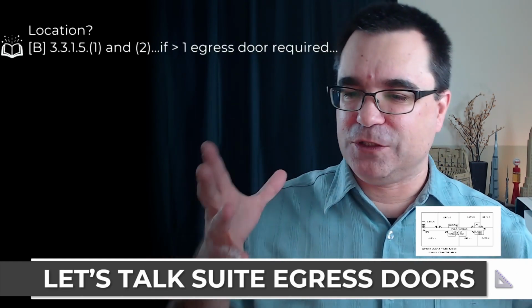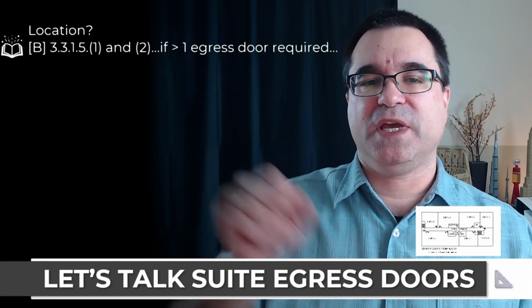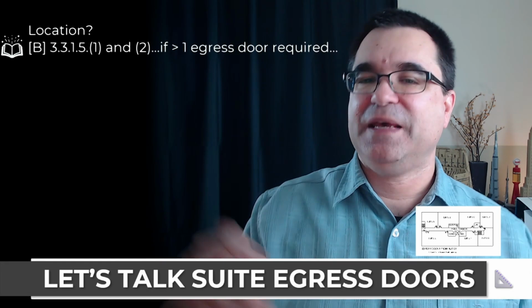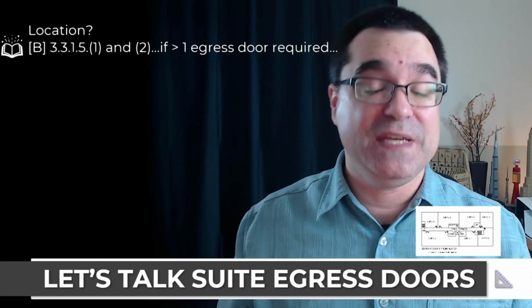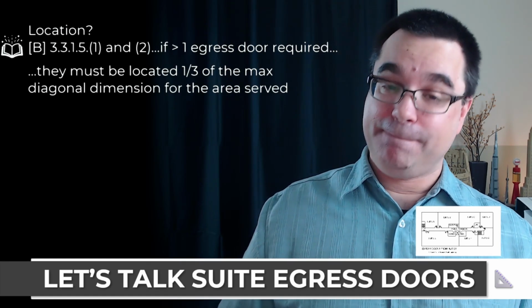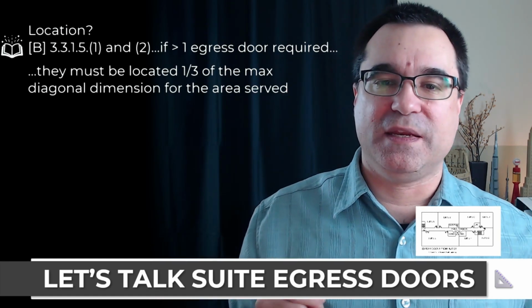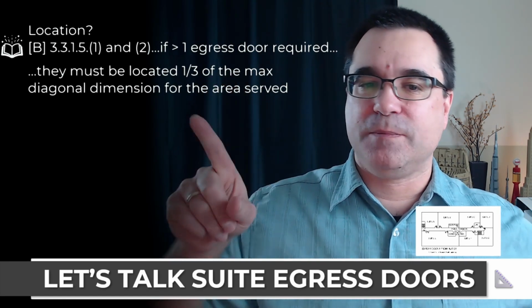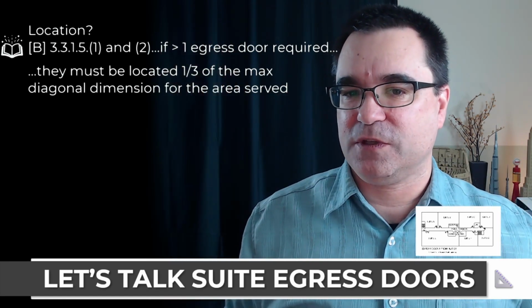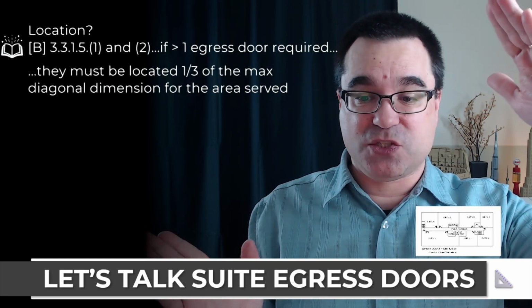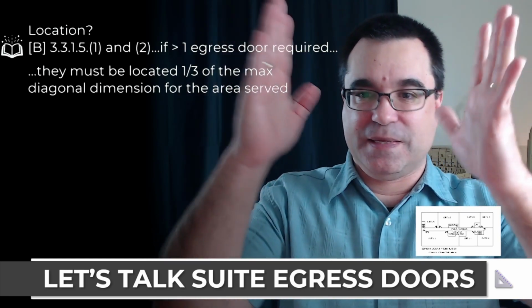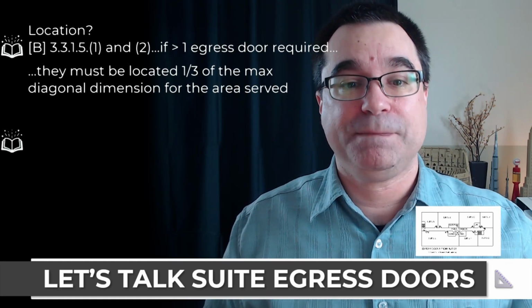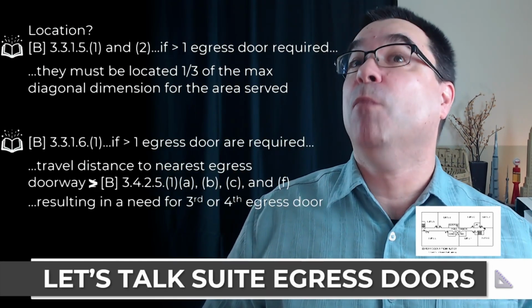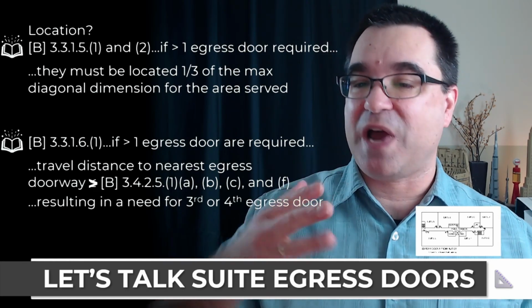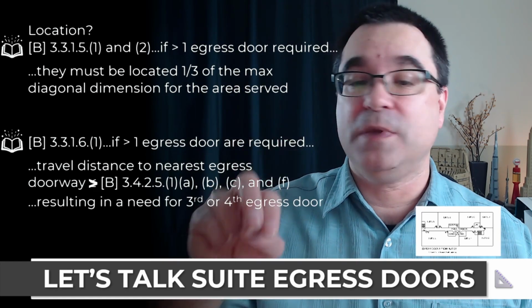Okay, where are the doors supposed to be in a suite? What is their location? According to these 2 sentences, if you find that in fact more than 1 egress door is required, then those egress doors have to be located so that 1/3 of the maximum diagonal dimension of that area is served. So you have to basically find that maximum diagonal dimension of that suite and take 1/3 of it as the maximum distance between the egress doors, which can then also end up meaning that you need more than 1 egress door if you want to make sure that the travel distance is reduced, maybe more than 2, maybe more than 3.